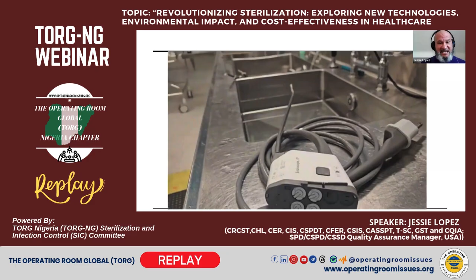We're now drying the device using pressurized air at a specific PSI rating to avoid any damages. We're drying out the lumens, the outside surface of the device, and then we're going to put it back into its instrument holding rack. So we want to neatly put that back in, again to avoid any damages. So I will show you that process as well. Again, utilizing clean hands. The rack is cleaned separately from the device because this too is a medical device. It is validated to hold this device so that it can properly be sterilized, because this device does require steam sterilization. So this rack is properly going to hold the device in place.